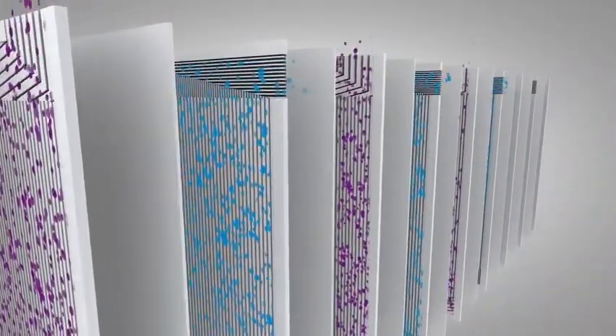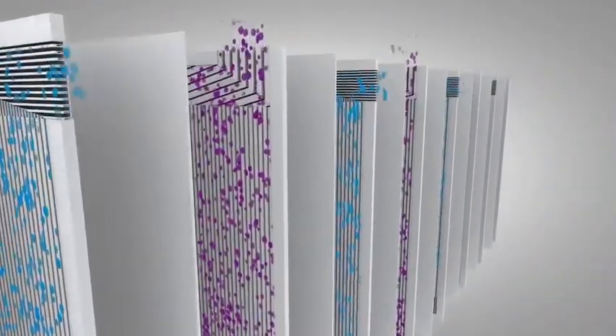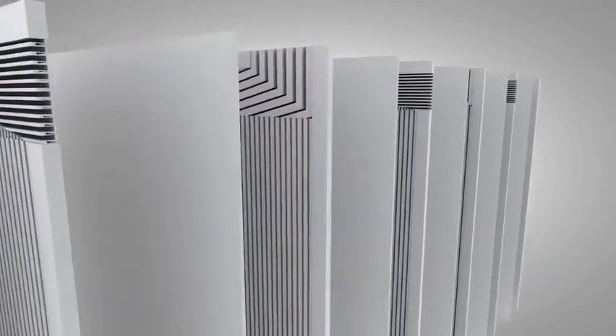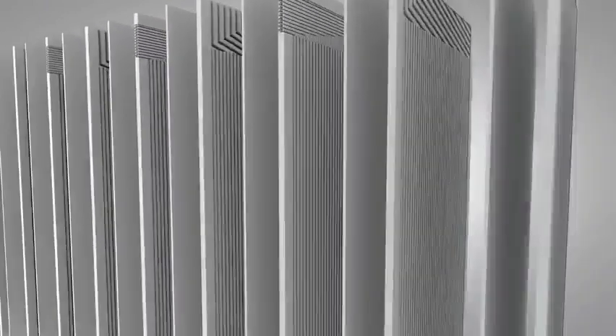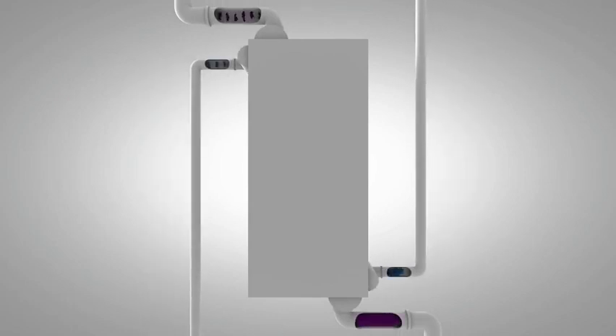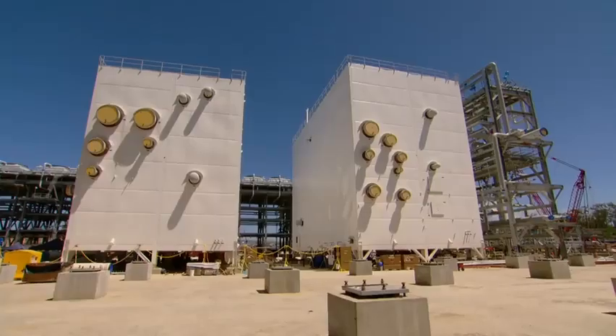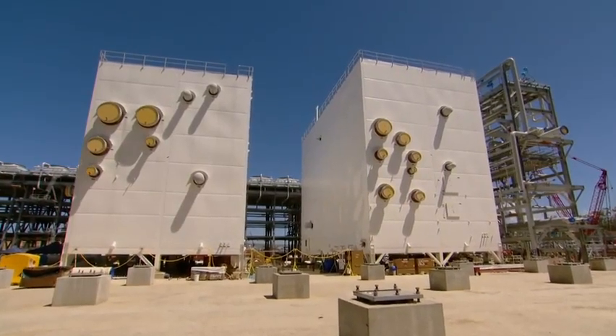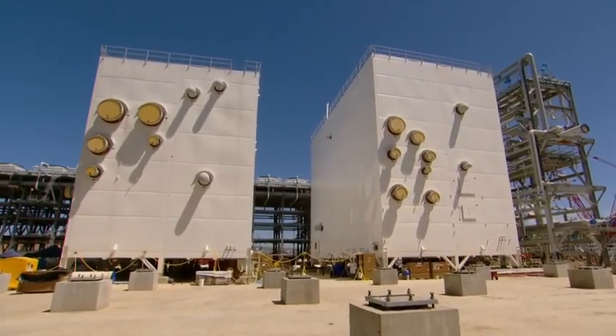These layers of fins and plates can be combined in many configurations. We arrange the flows so as to optimize the heat transfer. The aluminum plates are brazed together. We attach headers to the stack to direct the streams of refrigerants and natural gas. Then we install all this in a cold box—a heavily insulated box that keeps everything cold, giving operators more flexibility during steady and changing conditions.